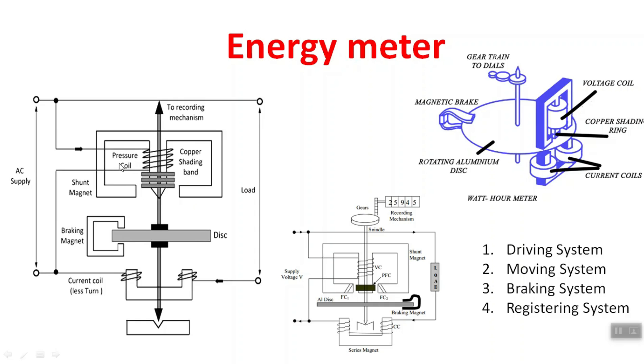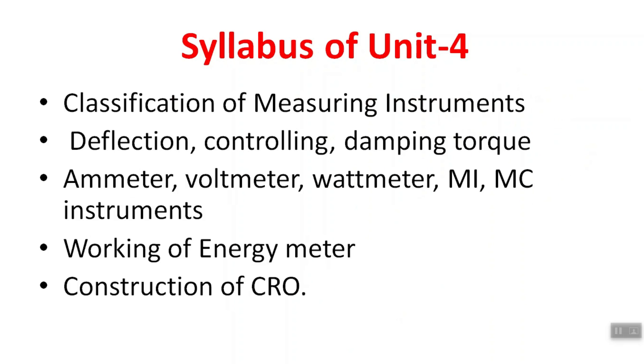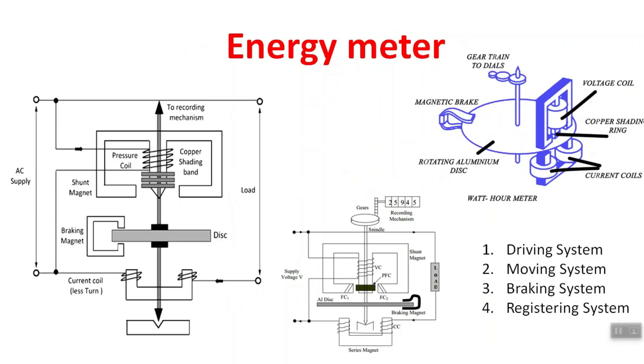The pressure coil is also known as the voltage coil. The voltage coil is connected in parallel with the load. The current coil is connected in series. Another part of the driving system is the copper shaded bars or bands, which are part of the upper electromagnet.